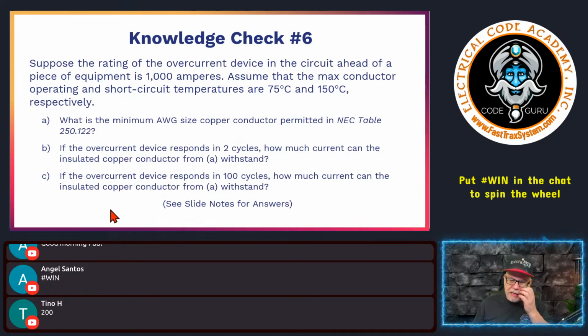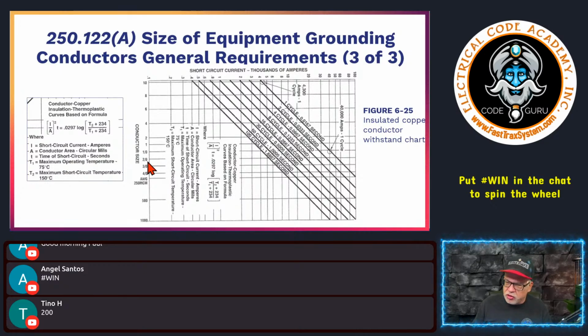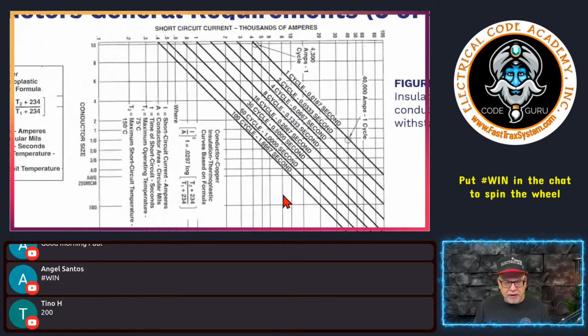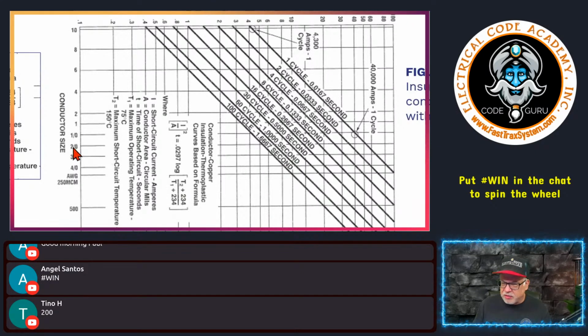Okay, let's go to the next question. Now, if the overcurrent device responds at 100 cycles, how much current can the insulated conductor handle? If it's at 100 cycles, it's still a 2-aught right here, and I know this is hard to see, guys. Is that a little better? All right, so here's your 2-aught. Let's go to 100 cycles, which is not good, by the way. And this is 100 cycles right here. Let's go up here. It looks like it can handle probably about between 5,000 and 6,000 amps.